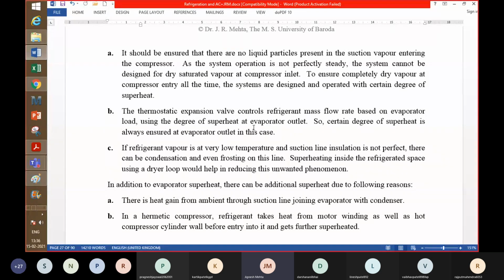Now the expansion device that was used in the system shown to you, it's a small system. So there it is a capillary tube, but one of the other popular expansion devices also work as control devices. They basically control the mass flow rate of the refrigerant through the device. There are two things working in opposite ways. One, the compressor is pushing the refrigerant, right? So that is giving a positive thrust, while on the other side, the expansion device is resisting that, right? It's a kind of resistance to the flow, and because of that, there is a pressure drop.